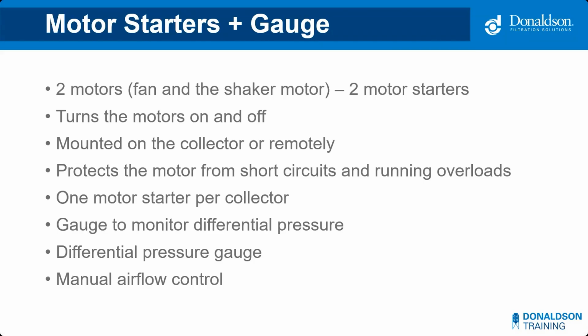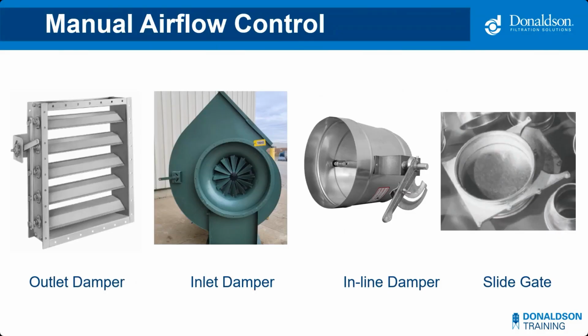I do want to take the time to introduce the concept of airflow control. With all the collectors we've discussed so far, it's typically done manually. The static pressure in a system will change over time due to the filters as they age. It's important to consider how you're going to control the airflow when you design a system to ensure that a designed airflow is maintained through this changing of static pressure.